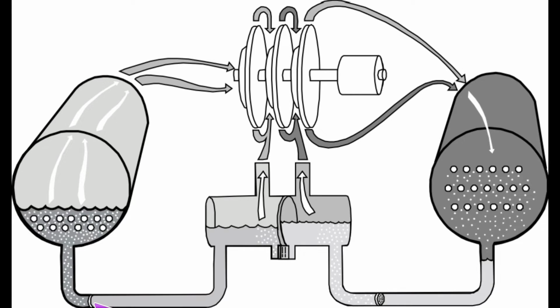And this is physically located at the evaporator itself. I mean, it's all right there. Where these sit are inside of flange bolt housings. And so there's actual flanges that'll bolt up, and where that flange bolts on either side of the pipe on the machine, that is the actual point at which that orifice is sitting. So just so you're aware, usually this one is right at the actual housing of the evaporator, like actually molded into the evaporator. It might have a short stub out, maybe, or it may just be a part of the evaporator housing that was kind of molded in.